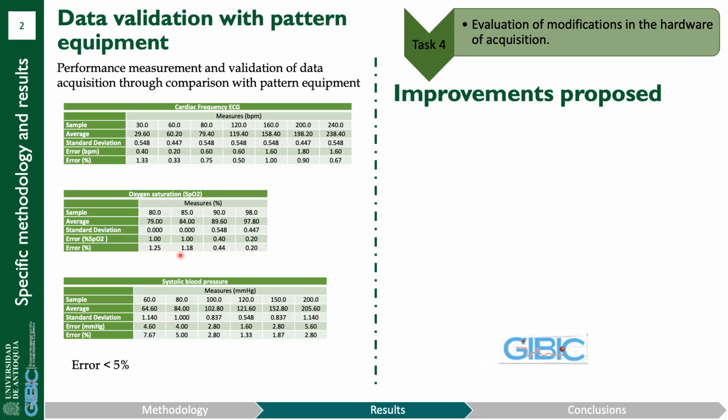Yes, I prepared these tables to give a general vision about the measures that we do. We propose the measurement, for example, in the ECG, of different heart rates, and this is simulated with a patient simulator, and the measures that we obtain with our device are in those ranges, and we apply standard deviation and error measurement of these signals.